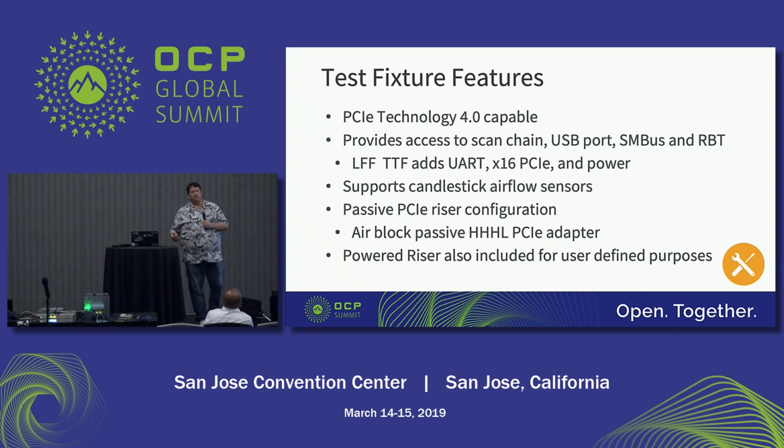then from a system level, we know what our system is capable of and whether or not we can cool it. It's something that Hemal will talk about later, in that all of that data is available before you hit aux power enable. That means that as a system vendor, I don't have to power that card unless I can cool it and I can power it. There are many things in there that give the system vendor the ability to look at the card and say, yes, it's good. Having a standardized test fixture for thermals is one of the key elements there.